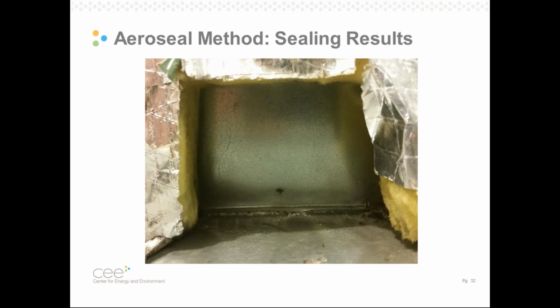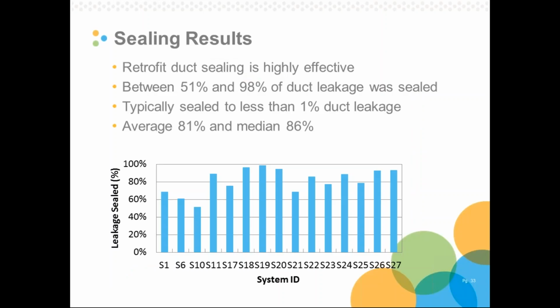And then you can also see this entire seam is shrouded in this external insulation. So this tends to be pretty common. The ducts are encapsulated by external insulation, and you actually don't see these gaps. In this case, we cut this away, and this seam used to represent about an 8 square inch hole in the ductwork that's now been sealed in this process. So these are some of the results of what duct sealing looks like in practice.